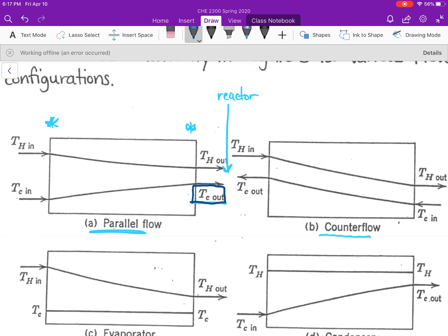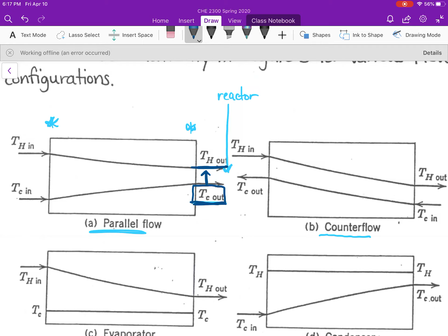If we operate in parallel flow, the temperature of this cold fluid will never be hotter than the temperature of our exit fluid. So we can put in a safety control based on the flow configuration of our heat exchanger. We will never be able to create a cold stream outlet temperature that is hotter than the hot stream outlet temperature.